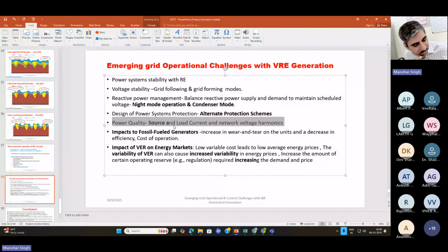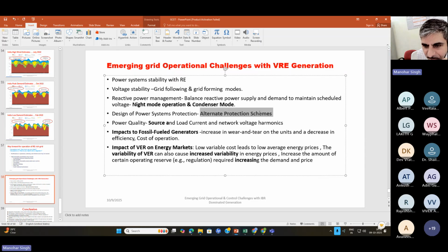And coming to the protection side, these resources have totally different protection requirements. We have a very reliable protection system, but that protection system works on the high short circuit current. And the high short circuit current is given by the synchronous machine only. If I don't have a synchronous machine on some power corridor, like a line coming from Leh to the NCR region, and on the other side I have only IBRs, and if any fault happens on that line, then there is no short circuit. If I place a distance relay at the Ladakh end, that will not detect the fault at all. Correct? Since there is no change in the short circuit current, that protection will fail.